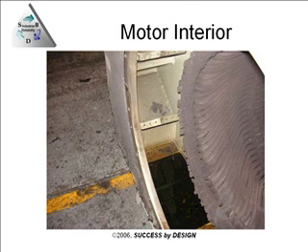And when we took it apart, we noticed a few things. For instance, the oil water line is all the way up to the winding. At this point, most of the oil has been drained away. Another thing I'd like you to note is that between the stator core and all the way out to the end turns of the stator, I have a fair amount of distance. There's also not much blocking in here.